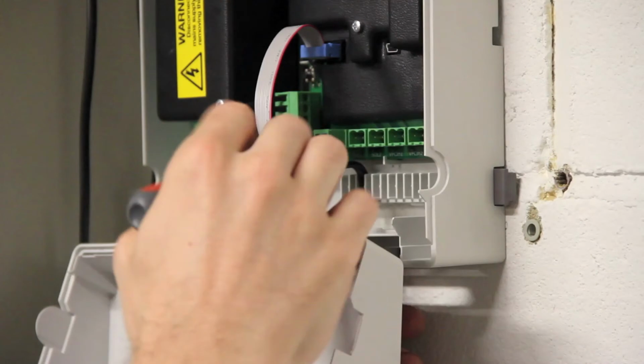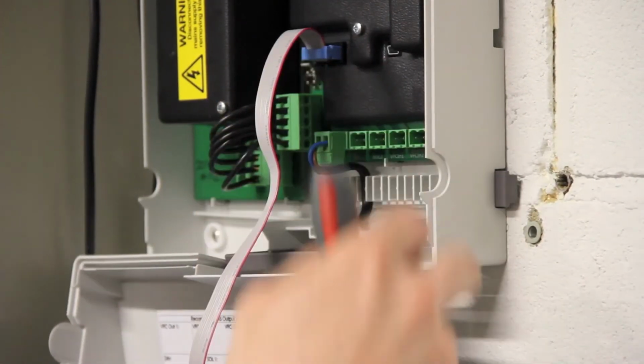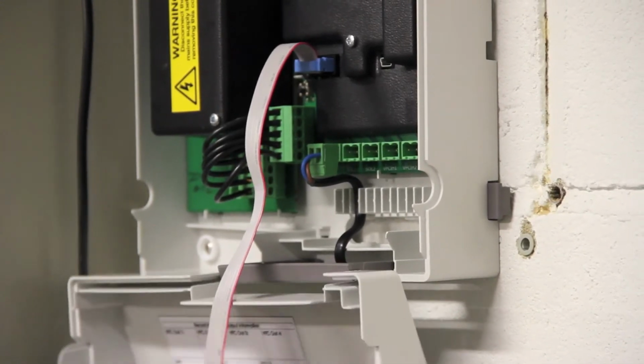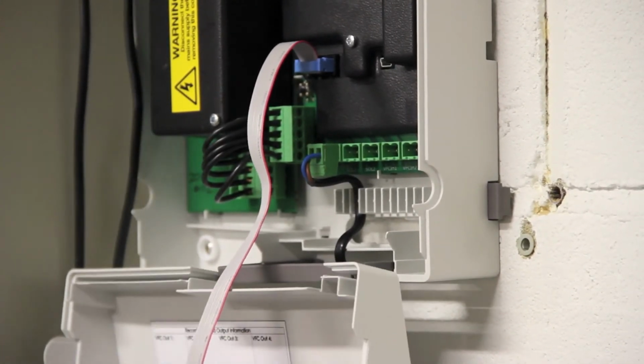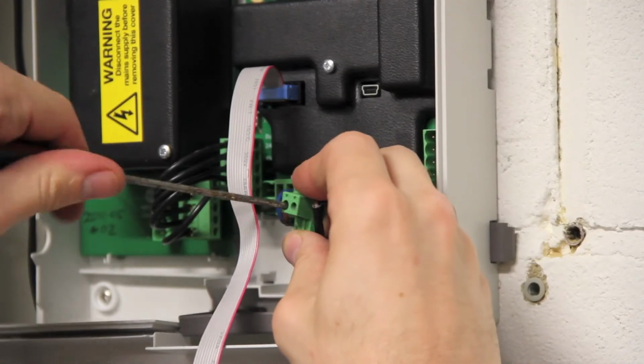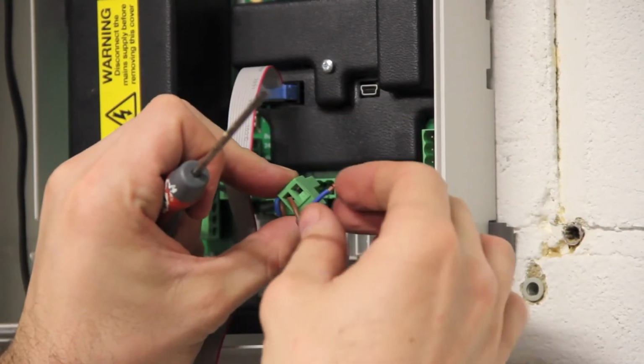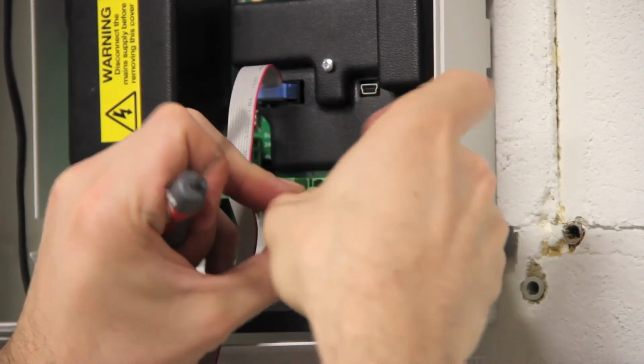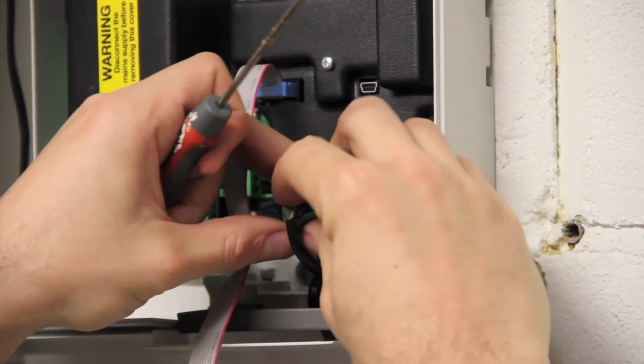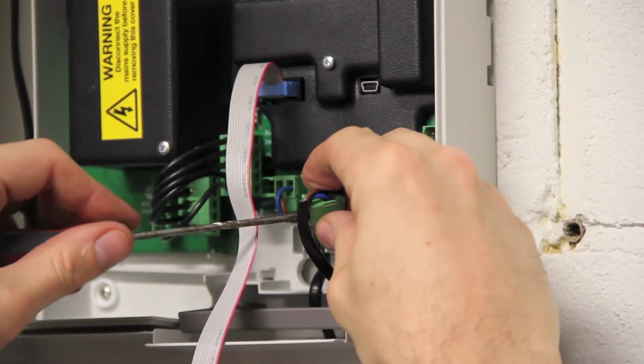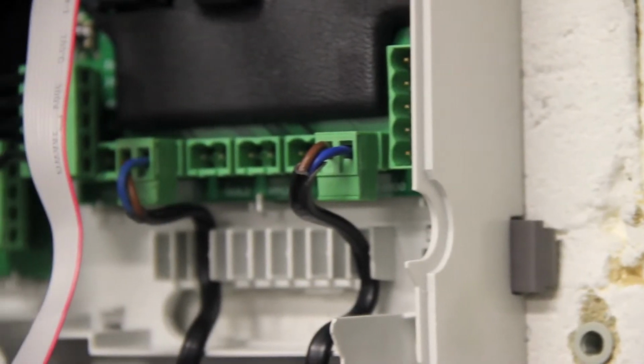Ensure the pilot valve remains disconnected to prevent possible filling before the tank level criteria has been set up. If the valve was connected when the power is turned on, the tank could begin to fill and overflow. Next, the wiring from the sensor assembly on the tank needs to be connected to the main control unit as shown. The system is now ready and power should be turned on once the lid has been refitted.